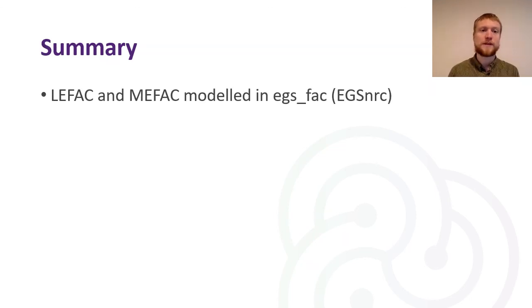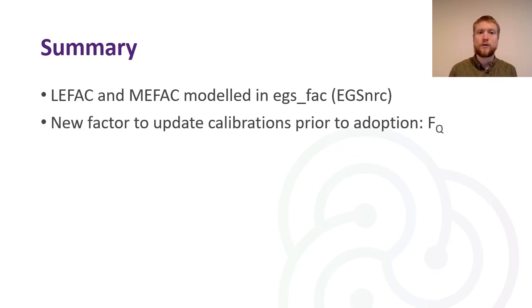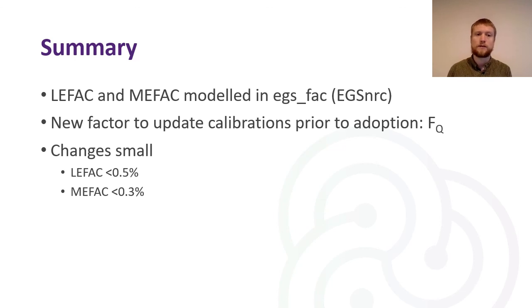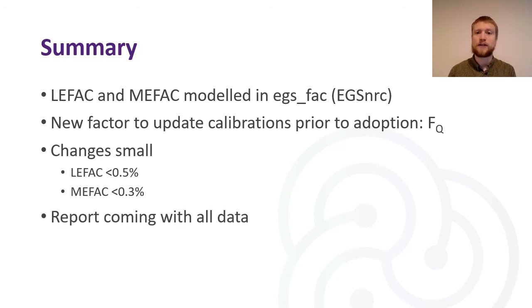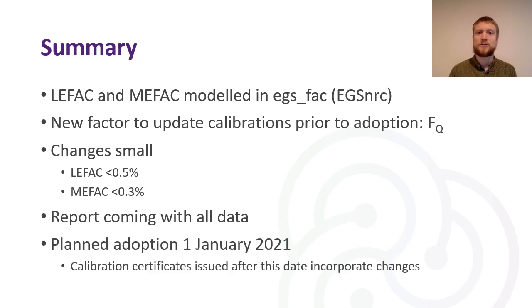So to summarise the important messages, we've modelled the LEFAC and the MEFAC in this new code egs_fac. We have a new correction factor to update all calibrations prior to the adoption of this update, which will be FQ. The changes for the air kerma will be small. We'll see LEFAC of less than 0.5% and the MEFAC of less than 0.3%. The report is coming with all the data and all of these FQ factors for all the calibration services we offer, and the planned adoption date for this change will be the 1st of January next year. And a reminder that any calibrations issued after the adoption of these changes will incorporate any of these changes in the calibration value you receive.